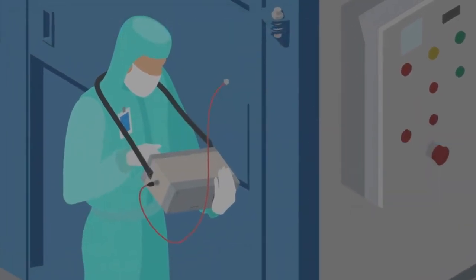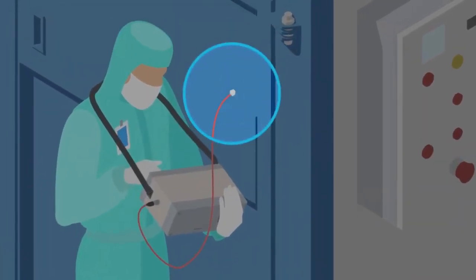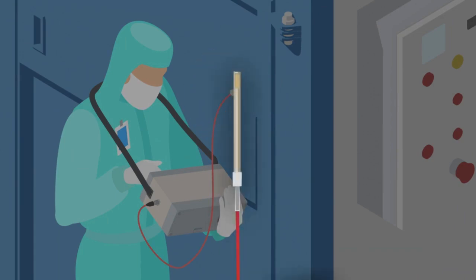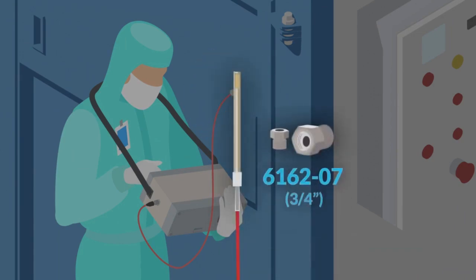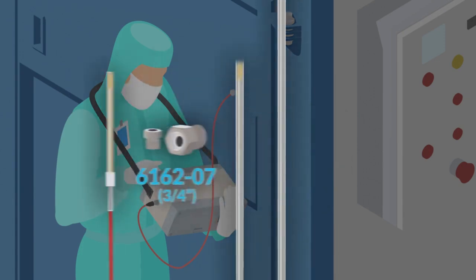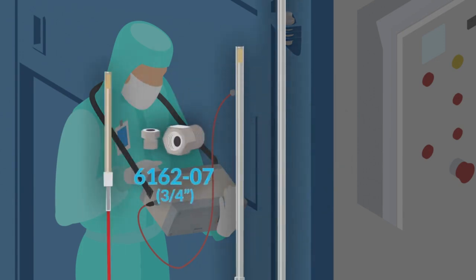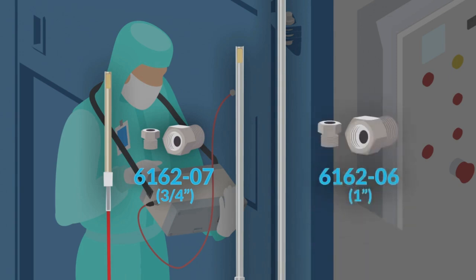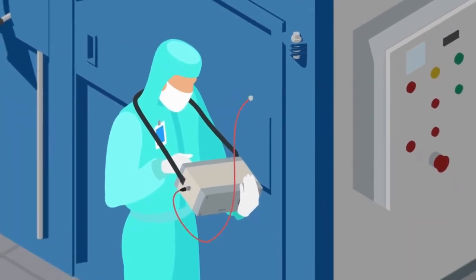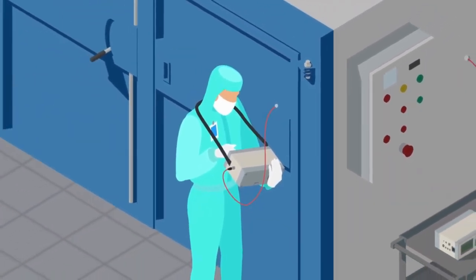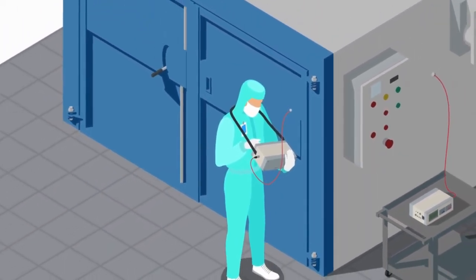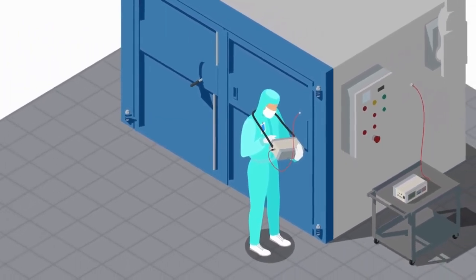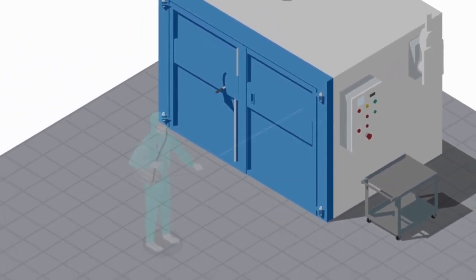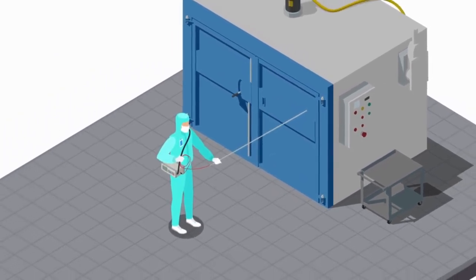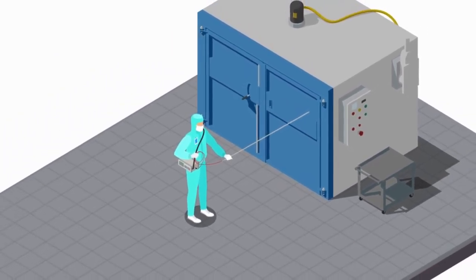When you want to directly attach your probe to the test environment, you'll need a compression fitting. Probe model 0203 uses the 3/4 inch model, 6162-07, and probe model 0204 and 0205 use the 1-inch model, 6162-06. The cabling for these probes have a max temperature tolerance of 392 degrees Fahrenheit. Keep that in mind before you think about exposing the cabling to the test environment. If you don't need to directly attach to the test environment, you can hold the probe at the measuring point, from a safe distance, using the extension rod designed for your probe model.